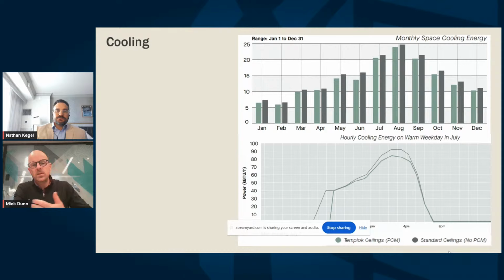So it might be, in some climates, more difficult to bring in ventilation for your cooling strategy in the middle of August. Even in LA we're able to do that, but perhaps if we relocate the building to an area that's a little more strenuous, like Palm Springs, which is inland California in a desert climate, it's not getting cool enough to simply use ventilation. So perhaps our energy savings might be more pronounced again in those shoulder seasons where we're getting natural benefit, but that doesn't mean we still can't drive energy savings in the peak of the year as well.